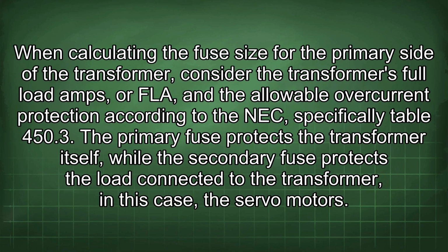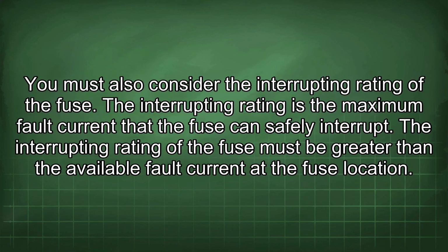When calculating the fuse size for the primary side of the transformer, consider the transformer's full load amps, or FLA, and the allowable overcurrent protection according to the NEC, specifically Table 450.3. The primary fuse protects the transformer itself, while the secondary fuse protects the load connected to the transformer, in this case the servo motors. You must also consider the interrupting rating of the fuse.